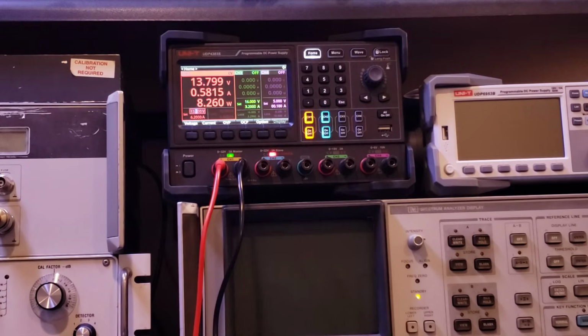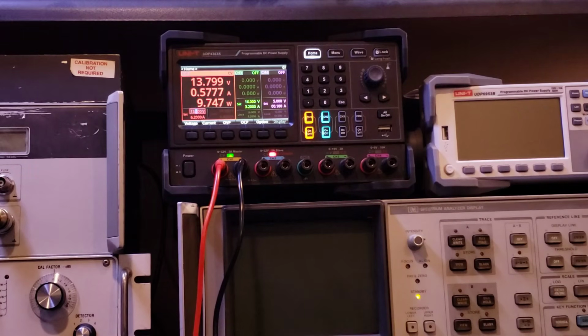What I'm interested in now is what the cutoff voltage and overvoltage protection voltage is for the inverter. According to the manual, the under voltage protection is right around 10 volts, and the over voltage protection is right around 15.5 volts. So let me dial down the voltage and see at what point the inverter cuts off.